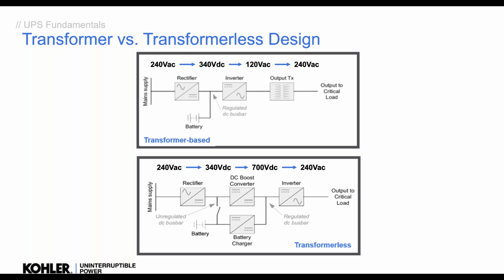UPSs over the last 20-25 years have changed quite a lot. Traditionally, we had this transformer-based UPS where we had a rectifier, an inverter, and a transformer. The transformer was there because we couldn't produce the required voltage without it. Modern UPSs now, it's not just us, it's most manufacturers are making transformerless UPSs. So this is where we have an inverter feeding directly out to the load without a transformer in the output. Loads of advantages to transformerless UPSs. They're smaller, lighter, critically much more efficient than the old transformer based ones.